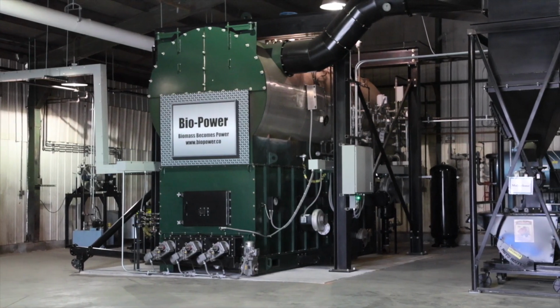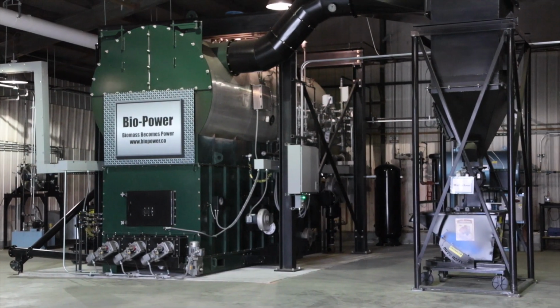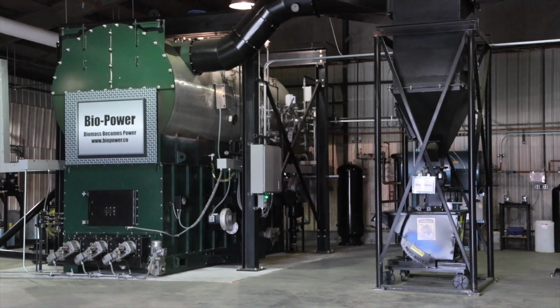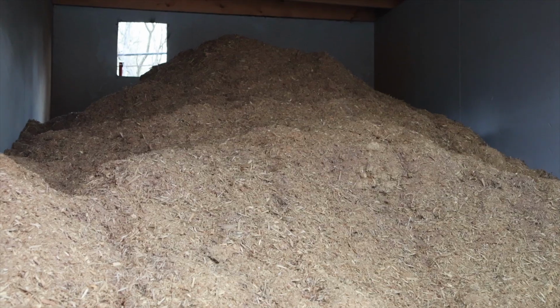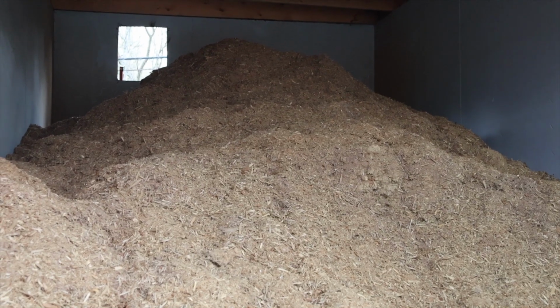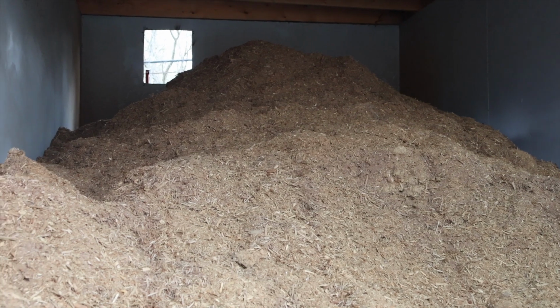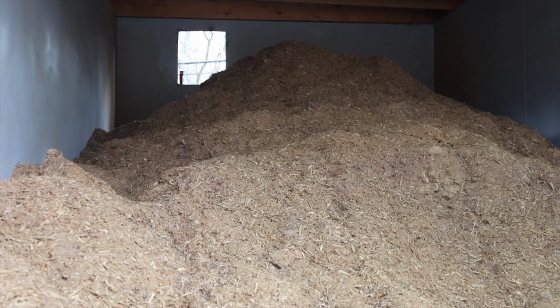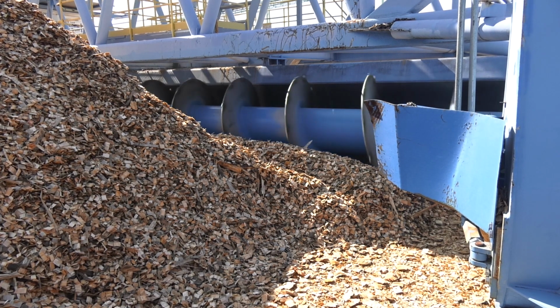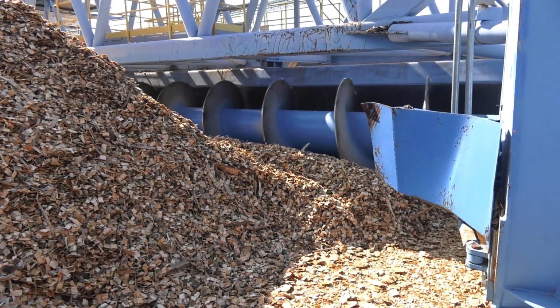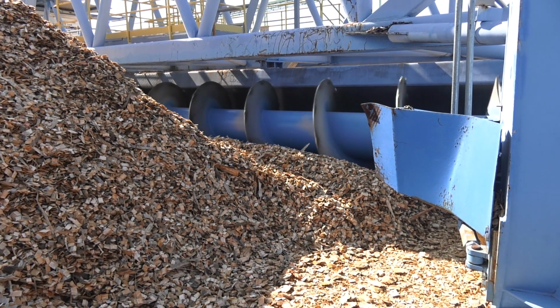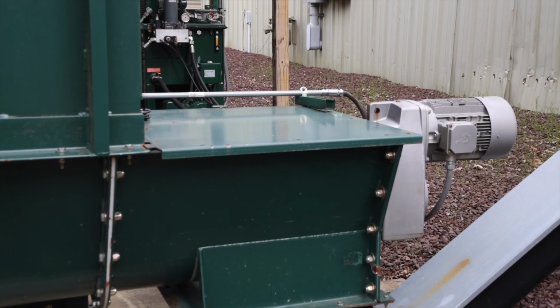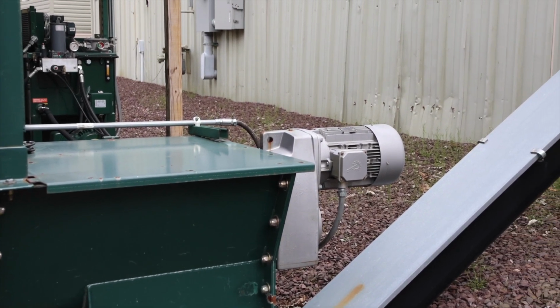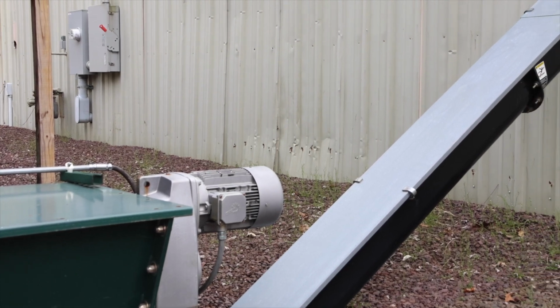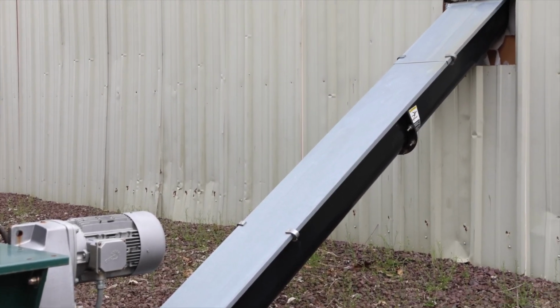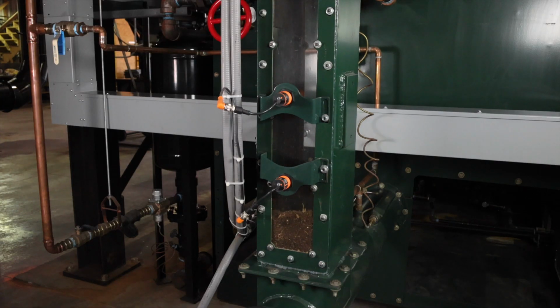Offering both heat and combined heat and power systems, the process begins when pre-sorted and pre-sized biomass is transferred from the fuel storage unit to the biomass combustion system by way of the fuel transfer system. This consists of a series of augers and airlocks designed to contain and move the fuel on demand. A chute equipped with photo eyes automatically operates all equipment used to transfer the biomass fuel.